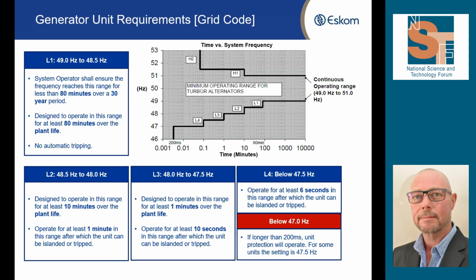Moving then down in frequency, if we go between 48.5 and 48 hertz, the tolerance in the design is only 10 minutes over the lifetime of the plant. So 10 minutes in 30 years is what they would be expected to operate for. For those first two, there's no tripping instantaneously, but if we drop below 48.5 hertz, after 1 minute generators start tripping.